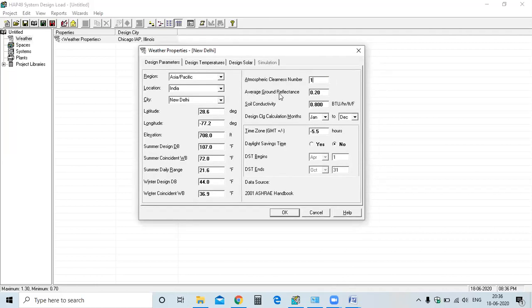Next, average ground reflectance means the coloring of the neighboring building. If the neighboring building is dark colored, it absorbs more heat and reflects less. If it's light colored, reflection is more and the heat load increases. I'll give you notes on what value to select, like 0.1 or 0.2, as per the condition provided by the architect.